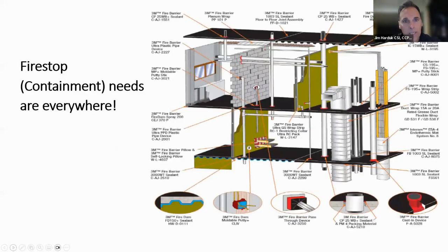So where do we find the need for a fire stop? Basically anywhere in a commercial building, anywhere you have a fire-rated floor or fire-rated wall assembly, and you have an item that penetrates through there. Again, it could be cable, could be pipe, it could be ductwork. All those areas need to be addressed and they need to be fire stopped. Next slide.